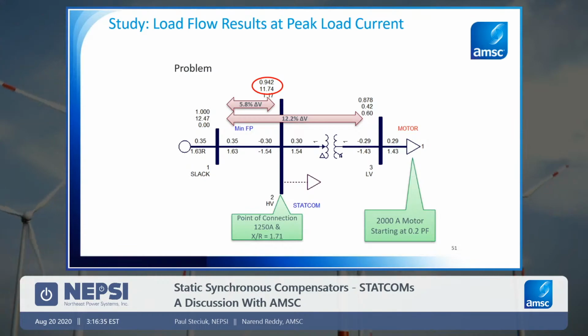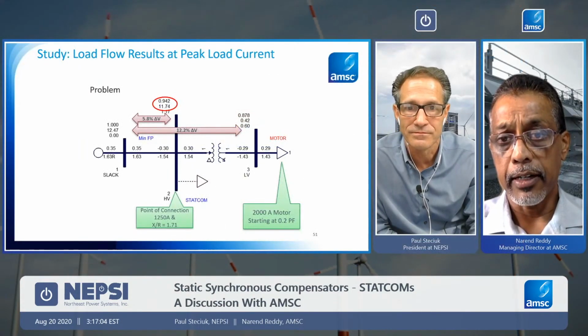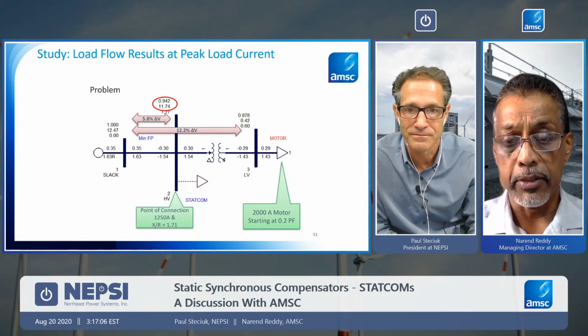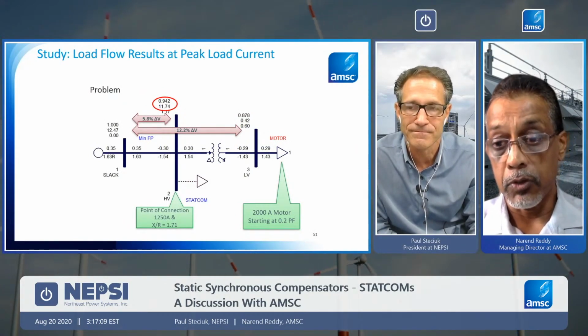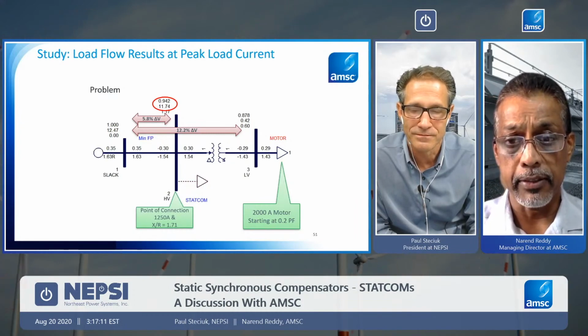So as you can see here, a simple analysis of the motor start application shows that the local facility connection point voltage drops by close to 6% during one of these hoist operations, and the same event results in the voltage at the motor terminals dropping by over 12%. And that's significant. Every time it operates, that's the level of flicker, the voltage variations happening on that grid.